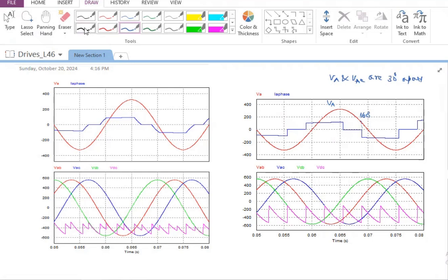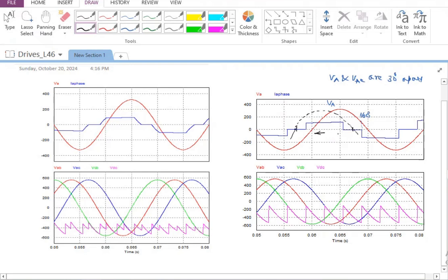And if I try to draw the fundamental current, it will actually have zero crossings like this. And if I am having 160 degrees, 130 degrees as alpha, you will also have the power factor angle to be somewhat like 130 degrees, or you can say 180 minus 130, 50 degrees leading power factor. That's what we are getting for the fundamental current, which is shown in black color.